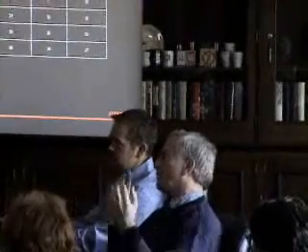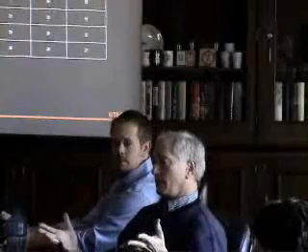Well, on the edges of the city, it would make a difference if it was off-grid. This won't be off-grid. It will still be connected for potable purposes. So the pressure will still be there, even though there are a lot fewer users. So it doesn't effectively save it on this particular project. And in the urban core areas, one of the problems is that we want to be averse to the risk of a fire. And so we have fire flow demand calculations that we make, and those so far exceed the daily water demands in a peak situation. We have to have that under pressure.